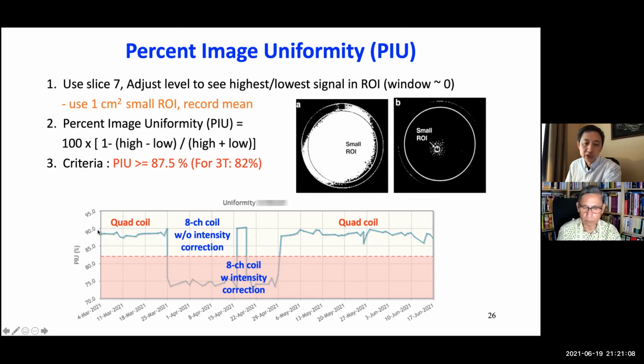We typically use a quadrature coil for our daily QC on this scanner. The uniformity is pretty good, but at a certain point, the quadrature coil went bad. So we used a multiple array coil. And of course, without intensity correction, the uniformity will be bad. And if we apply an intensity correction, it will be good. But we decided this was temporary, so we kept it without intensity correction. And then after the new quadrature coil arrived, it went back to the normal range.